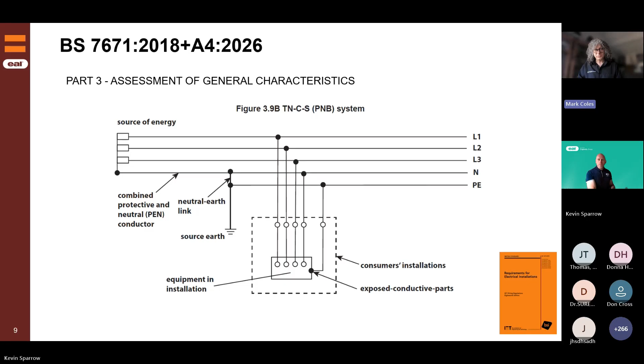Now there's not a lot on PNB. PNB used to be in, going back, and I think it was removed in the Yellow Book in 2015, but it might have been earlier than that. It was in as a reference to another format, another type of arrangement. But it's gone back in again, and all its reference really is a particular note in BS 7671 alluding to it. You might come across PNB in addition to PME, but in all cases where you do come across PNB, you'd say that TNCS conditions apply, and therefore you'd size your conductors in accordance with TNCS, i.e. PME. So that's all that's cropped up there.